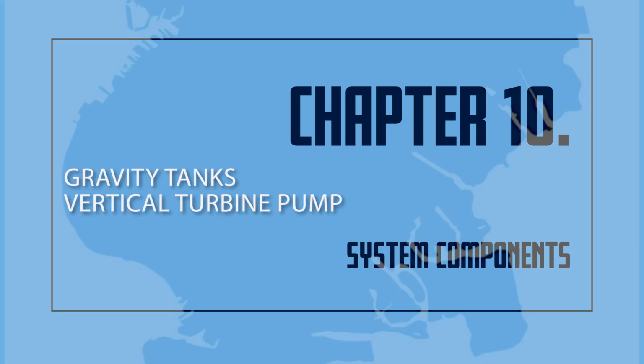Although the vertical turbine pump is capable of drawing water from wells, it is generally not recommended to use a well as the main water supply source because it may dry up without warning. Should the well dry up, it would make the turbine pump useless. It is better to draw water from the well and to fill a water storage tank. A fire pump should then be attached to a more reliable supply source, such as a storage or a suction tank. When using a pump to draw water from a suction supply source, it is important to ensure the water intake hose, foot valve, and screens are inspected regularly. Mud, gravel, and leaves may cause damage to the pump or obstruct the sprinkler system piping.